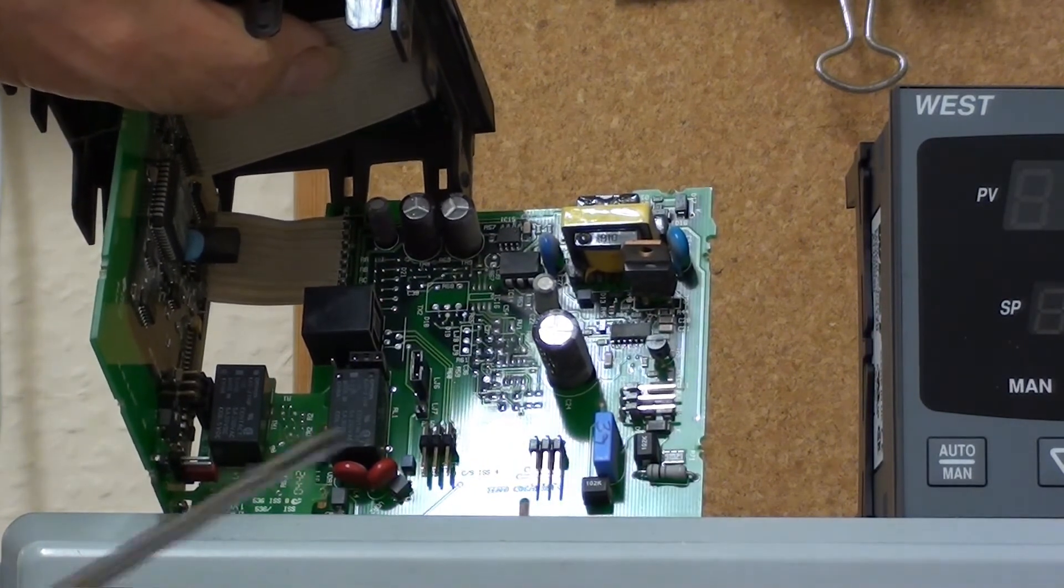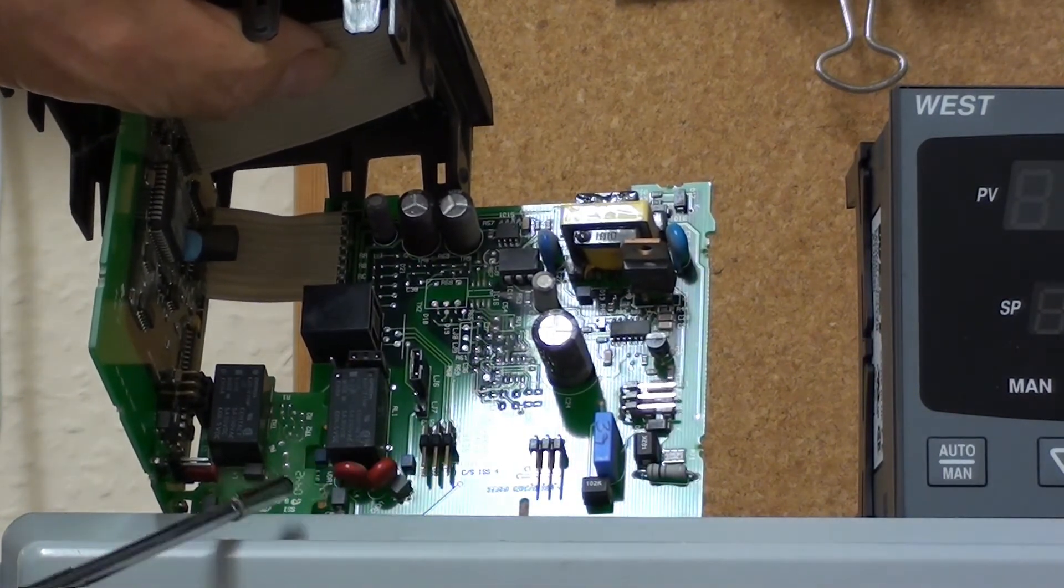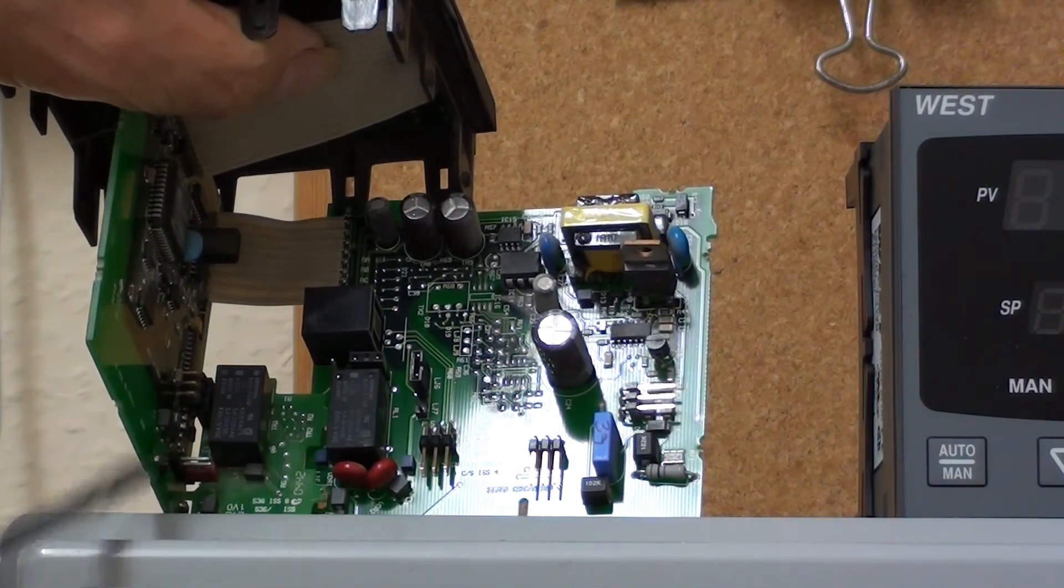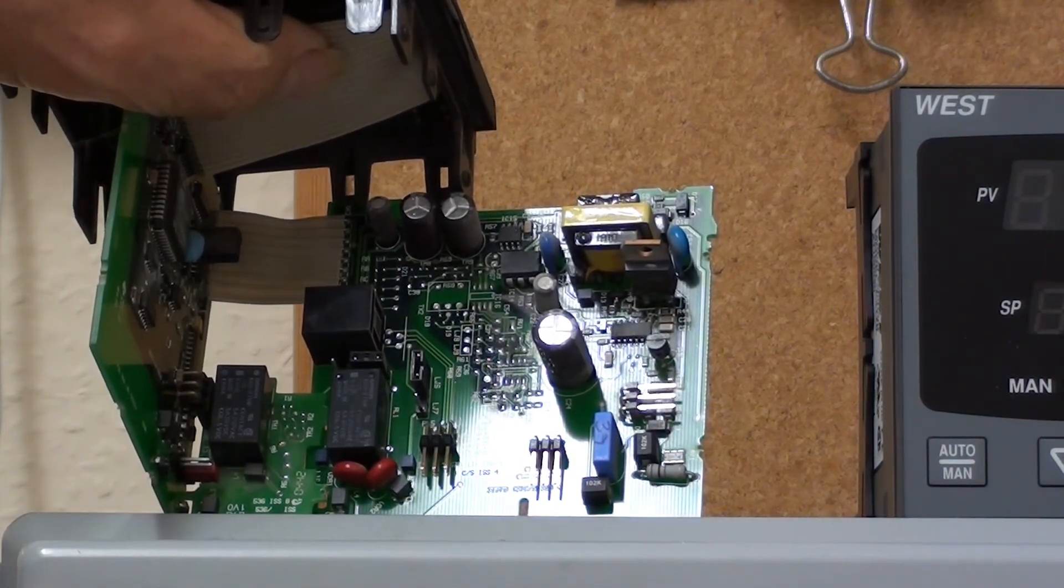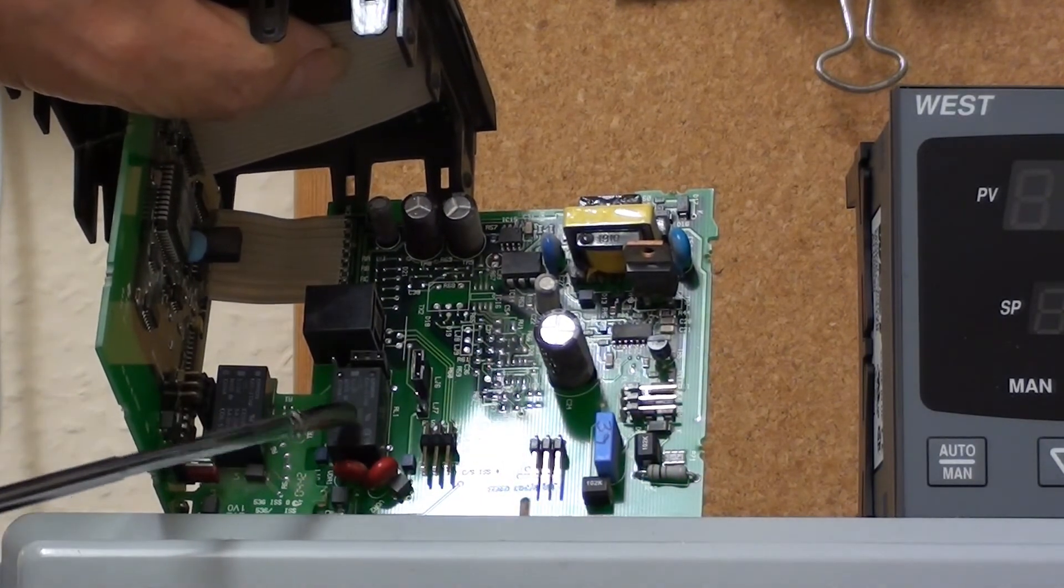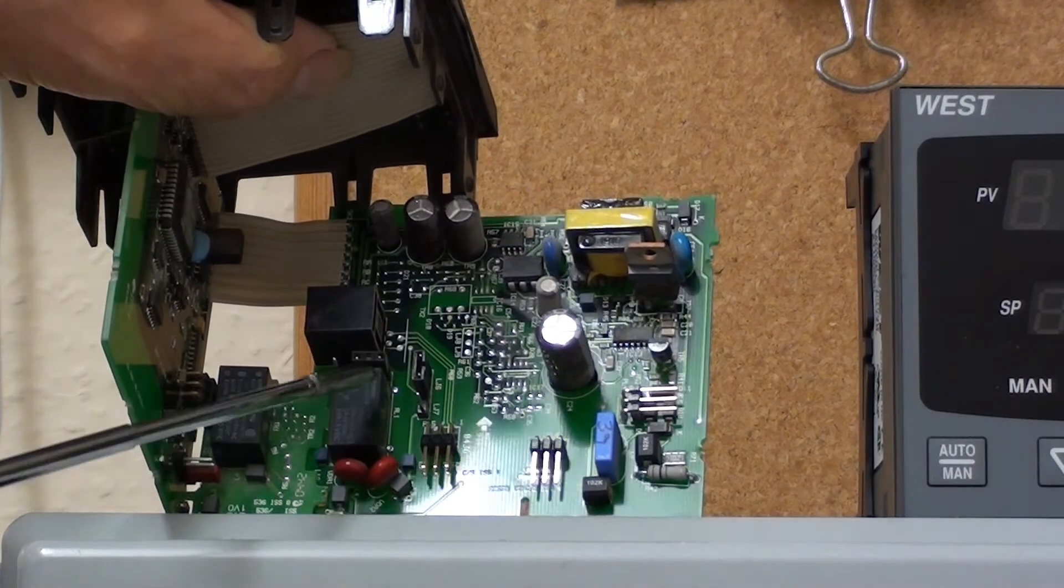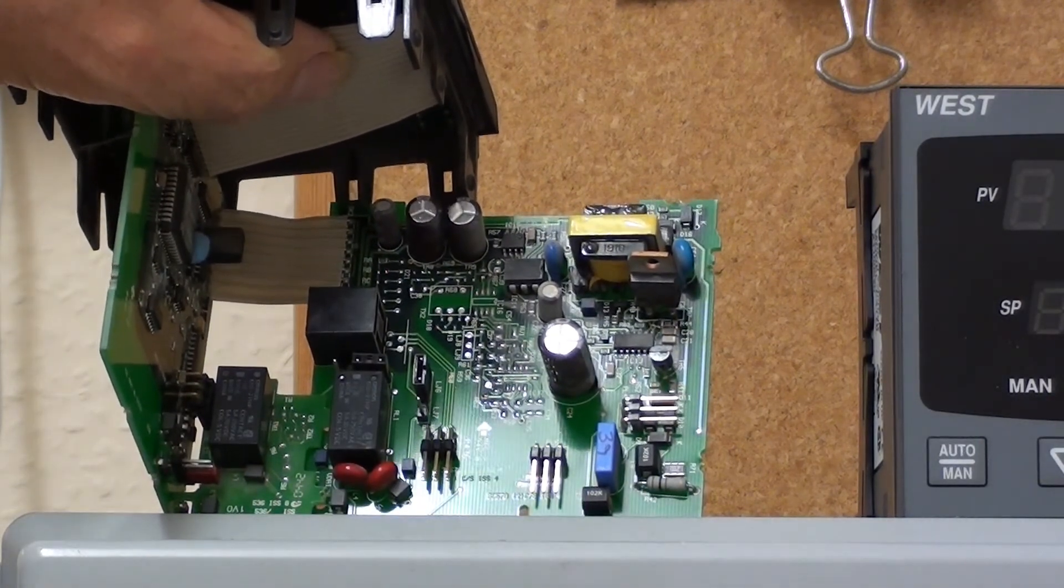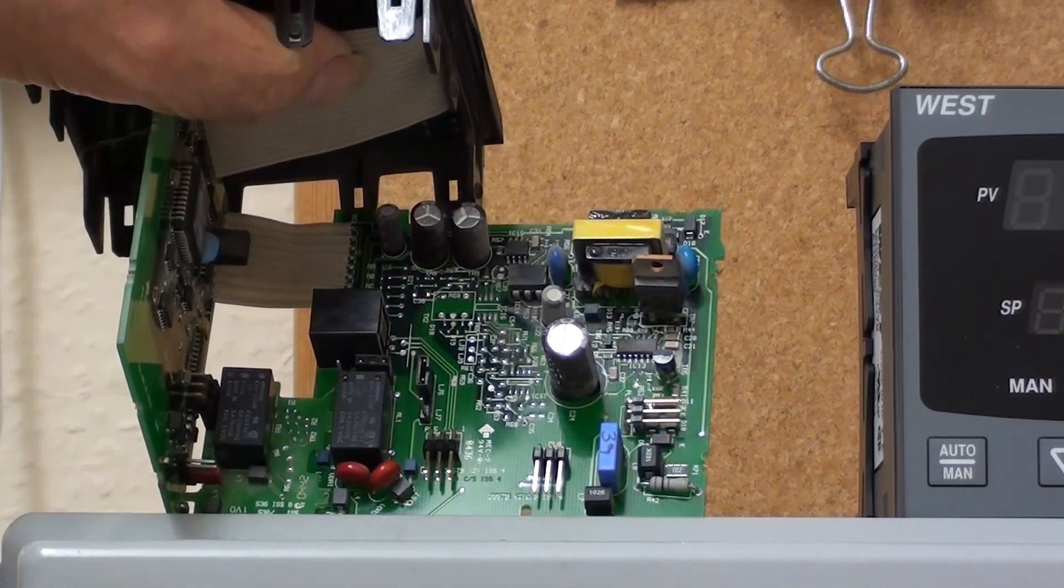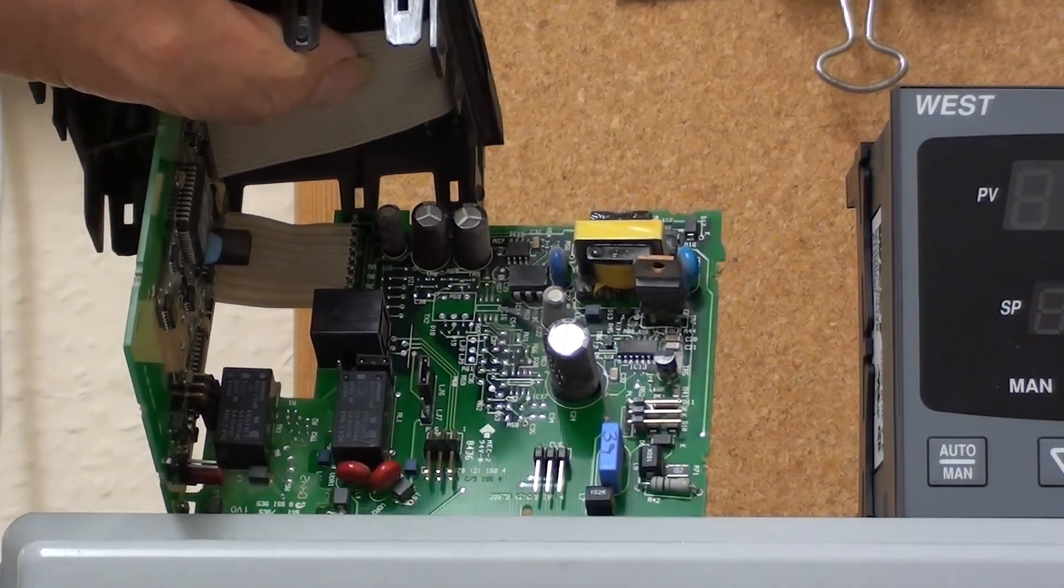And also on this board, the power supply unit board, you can see output 1. The output from this controller is relay output, and the output on output 1, this relay, is factory fitted. It's not a plug-in board. So if the relay fails, you need a new controller.